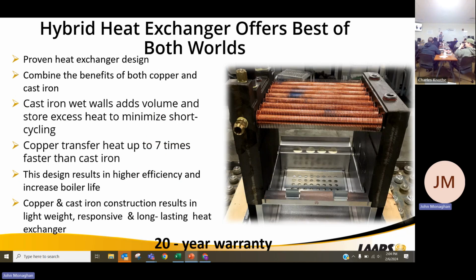The design kind of offers the best of both worlds with the heat exchanger. You have your cast iron wet legs on the outside of it and your copper tubes throughout the center. Instead of having all your intermediate sections on a cast iron product, which starts adding all the weight to it, this has its copper intermediate sections. Transfers heat much faster than cast iron, 7 times faster. Gets you a little bit higher efficiency with it. You're right around 84%, but it's going to be heating up that water much faster.